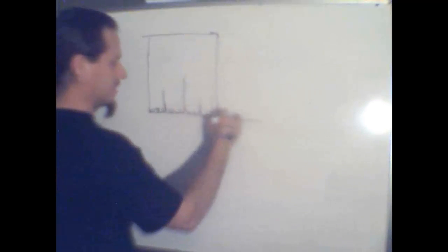We also do averages, standard deviations, and something called spectrum correlate, where we take the base peak — always the most intense peak. We don't care so much where it's located or how tall it is in absolute terms. What we want to know is how much taller it is compared to the noise, and how good the resolution is — how tall the peak is with respect to how wide it is at one half its height.